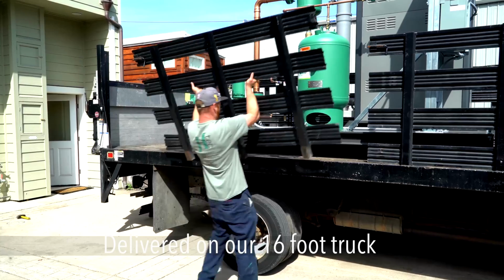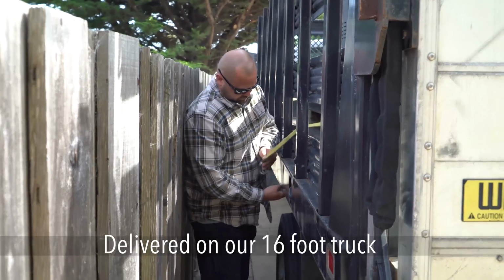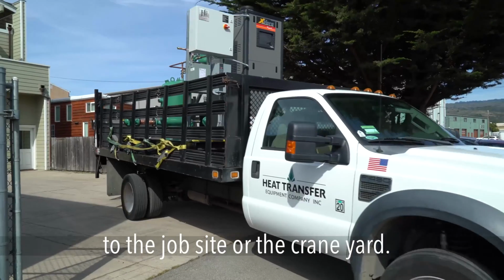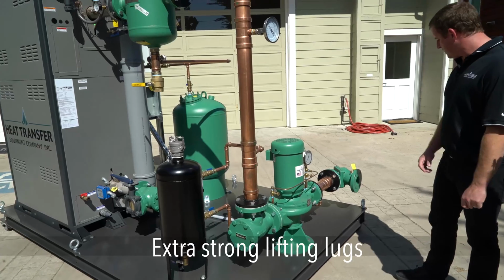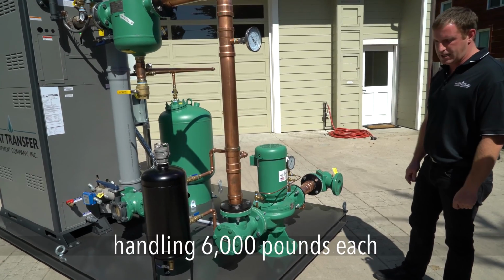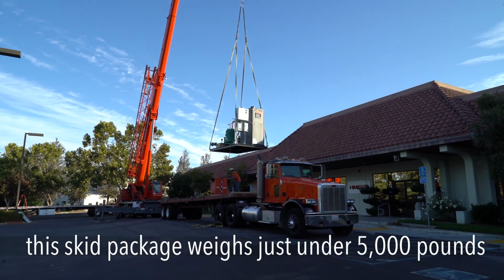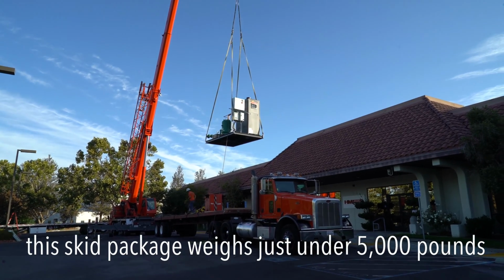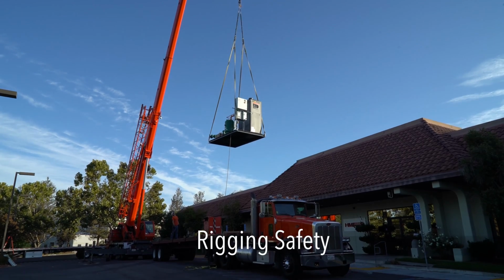We deliver it on our 16-foot stake bed truck. We'll load it up, strap it down, drive it to the job site. Lifting lugs are good for 6,000 pounds each in terms of shear strength. With 6 of them, this package weighing just under 5,000 pounds, rigging safety.